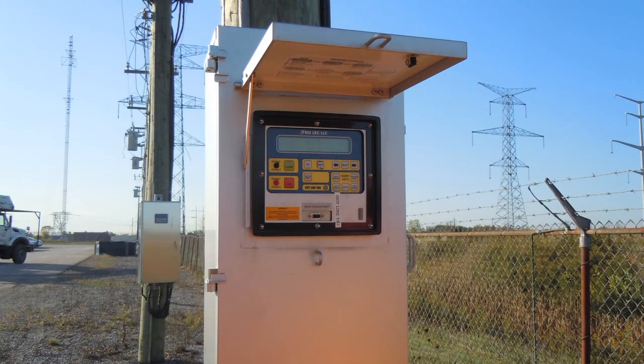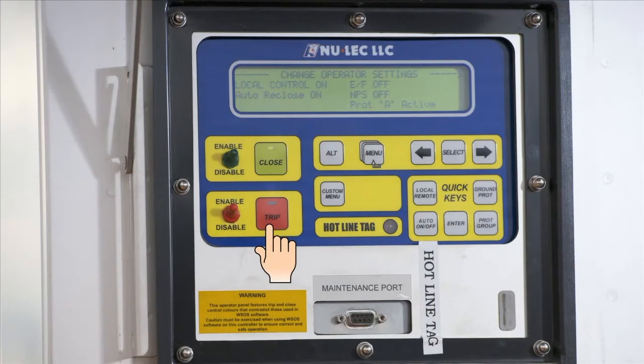Panel on key turns the operator interface on. The operator interface also will turn on when the cubicle door is opened. Trip key generates a trip request to the processor when the panel is active. A lamp is embedded in the key to indicate its operation. Another lamp is used to indicate whether the key's operation is disabled.